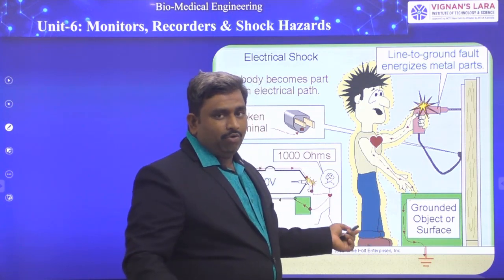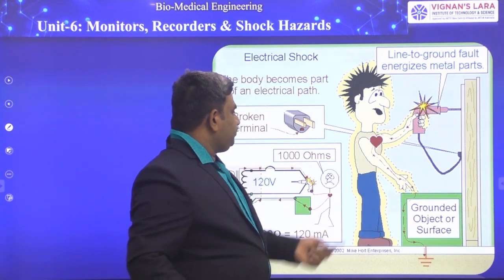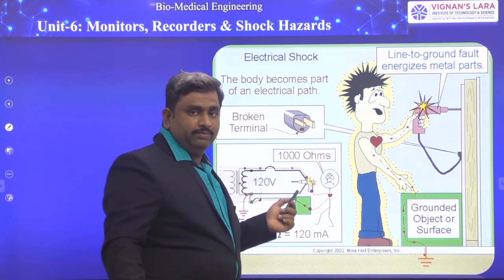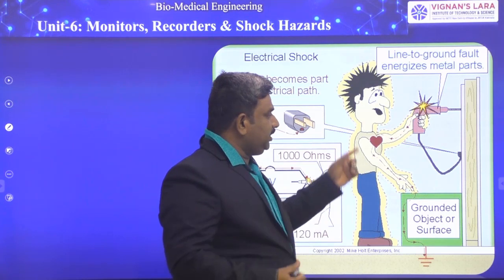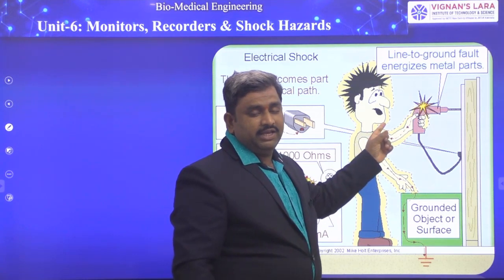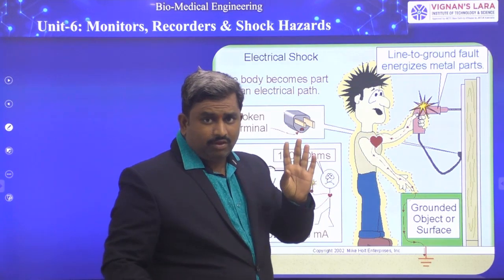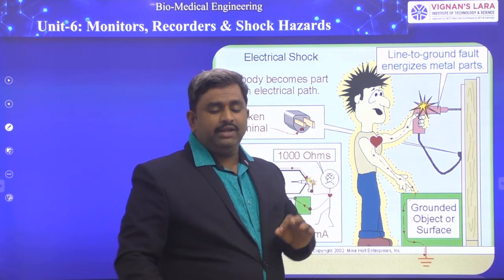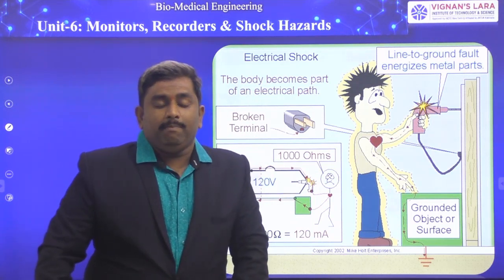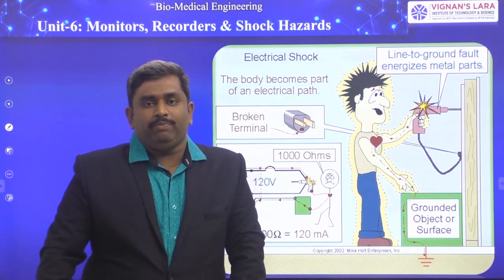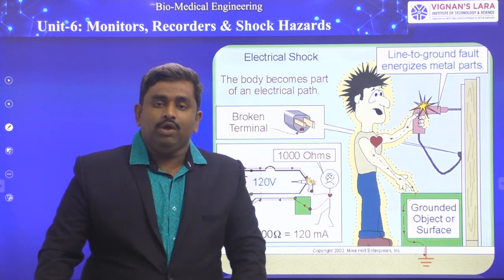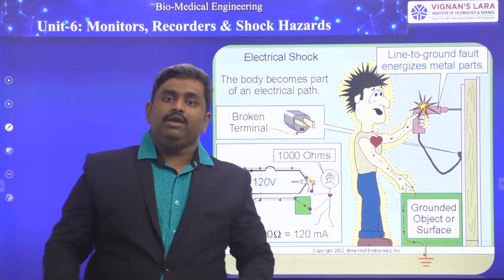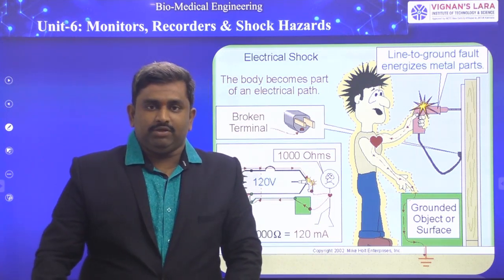If proper grounding is not available, then the patient is going to be shocked. When operating, the equipment is connected with only neutral and line conductor. Generally electrical leakage will be there in every equipment, but the leakages have to be grounded. That means we have to provide a grounding path. If you are not providing the grounding path, then it will take your body as the grounding path.